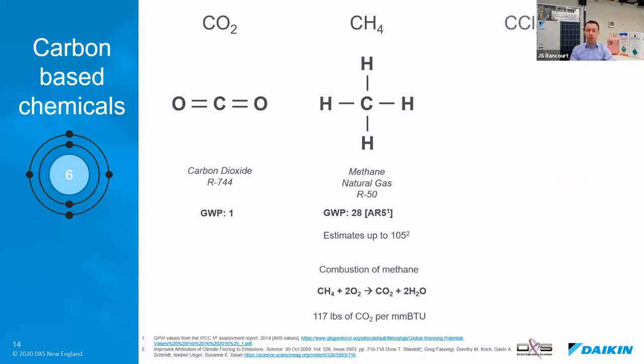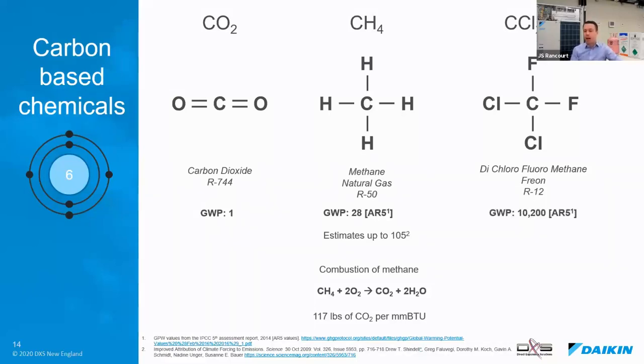So let's introduce our first refrigerant here. This is dichlorofluoromethane, also known as Freon. This is essentially the first safe refrigerant synthesized back in 1930. This is known as R12. The GWP of R12 is over 10,000. It's extremely high. Now it's important to note that this CFC is now fully phased out, but it was not due to its GWP. We'll talk about that in a minute.